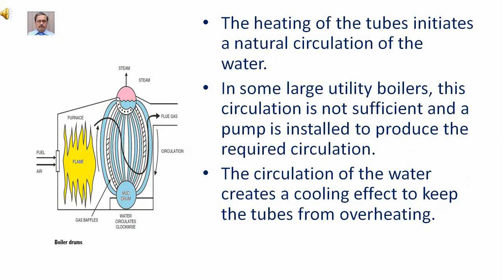The heating of the tubes initiates a natural circulation of the water. In some large utility boilers this circulation is not sufficient and a pump is installed to produce the required circulation. The circulation of the water creates a cooling effect to keep the tubes from overheating.